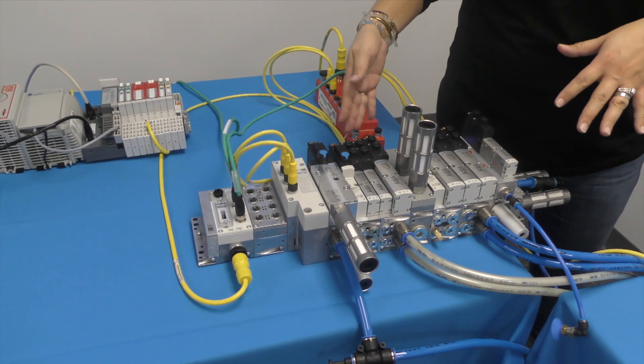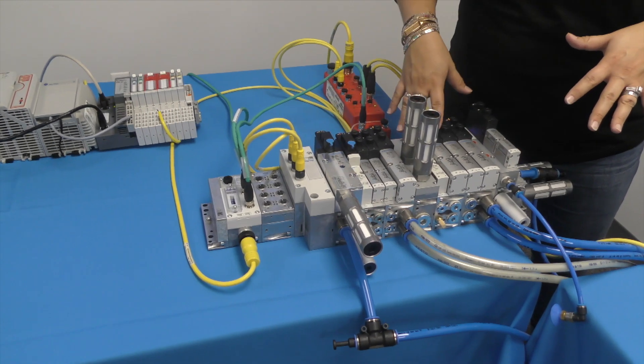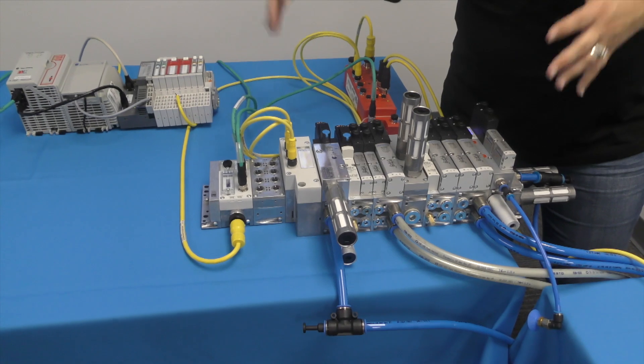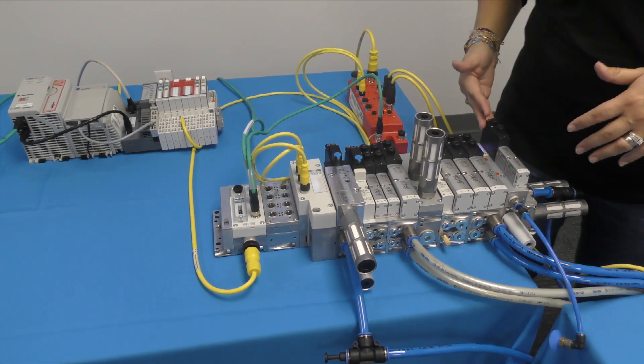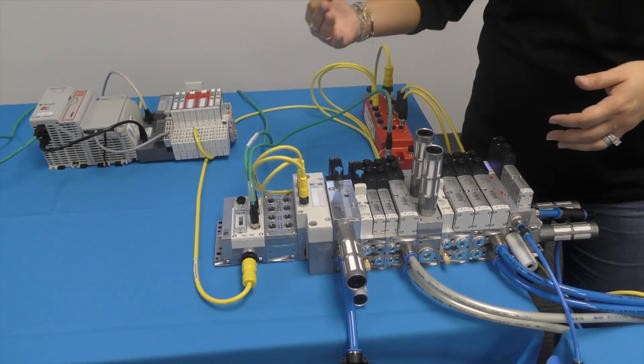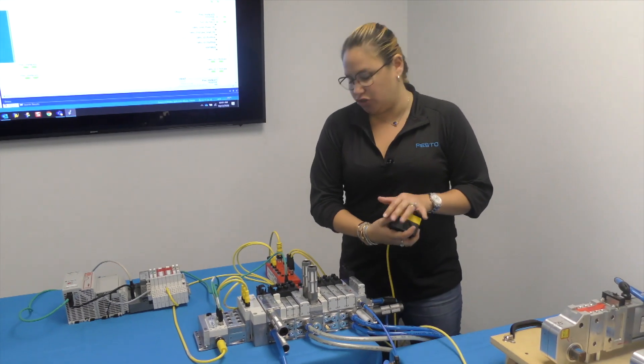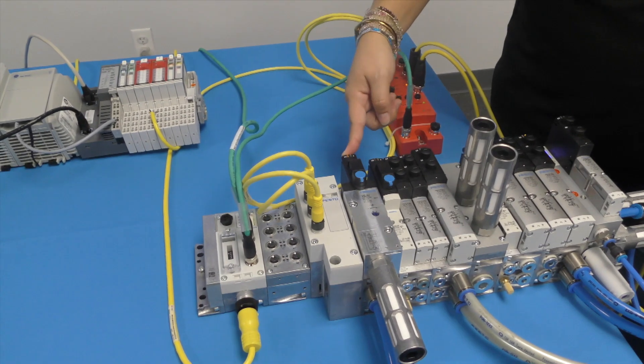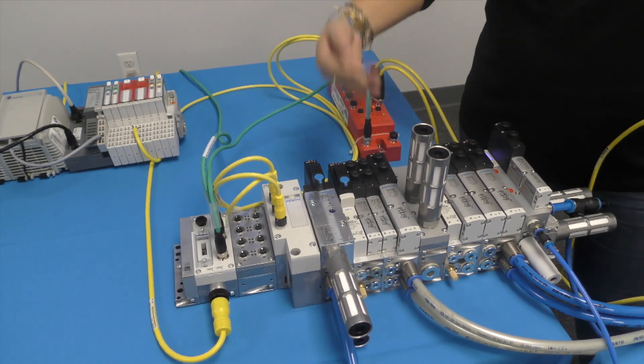We have a lot of LED signals going on right now. These signals indicate whether there's pressure present in the valves or not. In this example, we have three different safe power zones in the manifold and one additional power zone that includes the vacuum generator. The soft start quick exhaust valve is feeding all of the valves downstream, and we can set the fill time by adjusting the flow control. We also have a pilot control valve per zone. If I push one of the E-stops, one zone will completely stop — you can see the LED change from orange, which indicates pressure, to showing no pressure in this zone. Once I reset the zone, you can see the pressure is back.